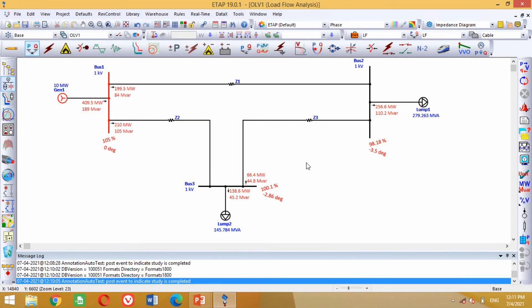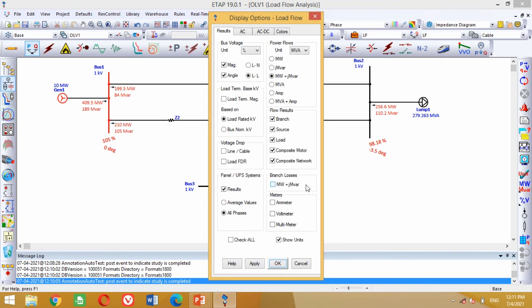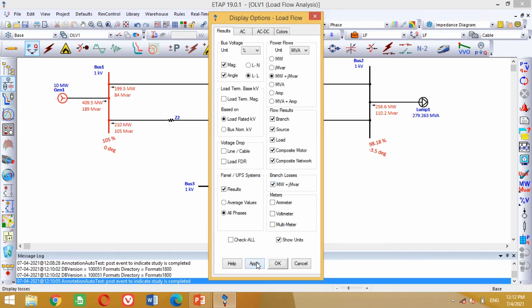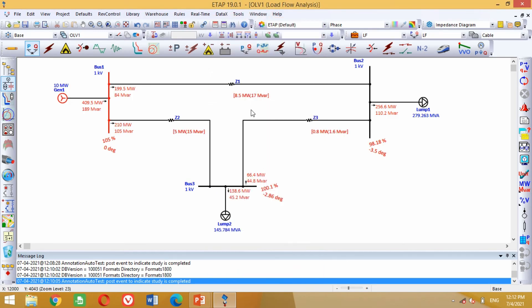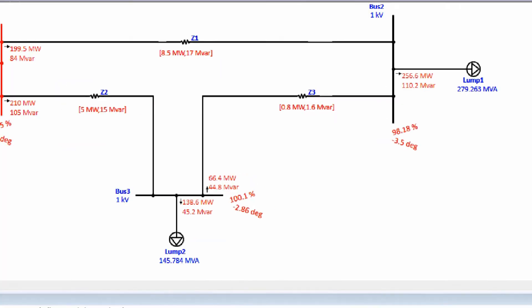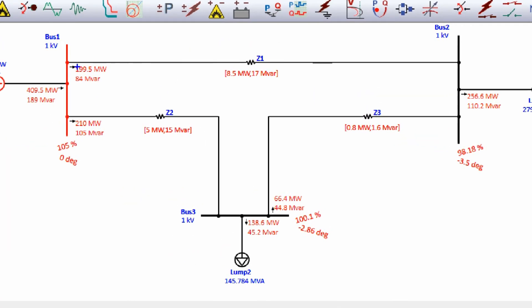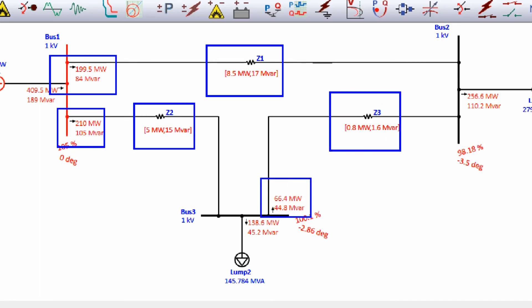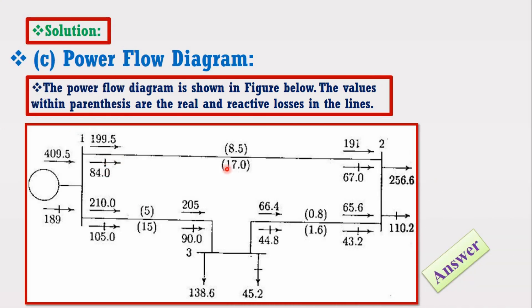Now we need to include the line losses in the model. For this purpose, again click on this display button — a new window will appear. In this window, click on these branch losses to include real and reactive power losses in the transmission lines. Then click on Apply and press OK. You can see now it has included the real and reactive power losses in the various transmission lines of the model. Now compare the results of power flows and line losses of the whole model with the example answer — you can see all the results are correct.